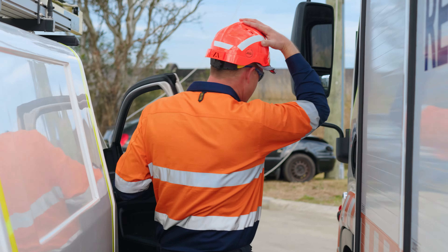Now let's look at another scenario — fire. Whether it's a property fire like a house fire or a bushfire, the heat from the flames can damage electrical infrastructure and bring down power lines. Extreme caution must be taken when approaching a fire site. In the case of a property fire, the proper course of action is to turn off the power supply at the main switch. Keep in mind there may be more than one main switch. Illegal wiring can sometimes be present that isn't controlled by the main switch, leaving power energized to the property. In rare circumstances, generators are used to supply properties with power, so be aware of this. Perform a hazard and risk assessment to identify any potential hazards.